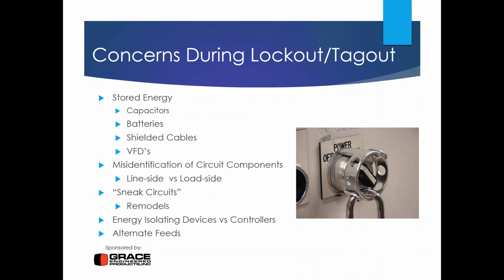Last but not least, some concerns during lockout tagout. Well, stored energy is always a potential challenge. At the top of the list is really capacitors. They are, by design, storing electrical charges. So some capacitors have a grounding reactor or a grounding resistor with them that will bleed the voltage down on the device in 5 minutes or so. Others do not. But capacitors always represent a possible source, and they have to be isolated if you're going to do lockout tagout. Of course, batteries are the very definition of stored energy.